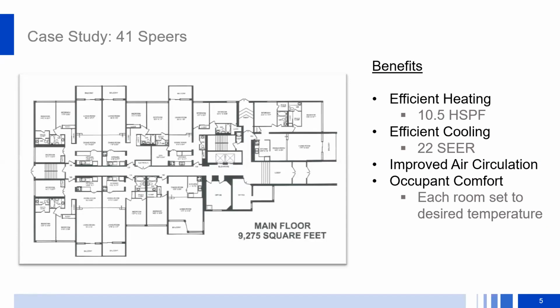Here's a floor plan at 41 Speers. Not only are there 1, 2, and 3 bedroom layouts, but they all have slightly different configurations, which made it a little difficult on the installer side to deal with that variance. The main benefits and goals of the project were more efficient heating and cooling, improved air circulation—some tenants in upgraded suites mentioned they could really feel the heat or cold instantly after turning on the units, whereas the PTAC would take a while to kick in—and also occupant comfort, since each space could be controlled separately, so the living room and bedrooms can be set to various temperatures for better overall comfort. Next slide, please.